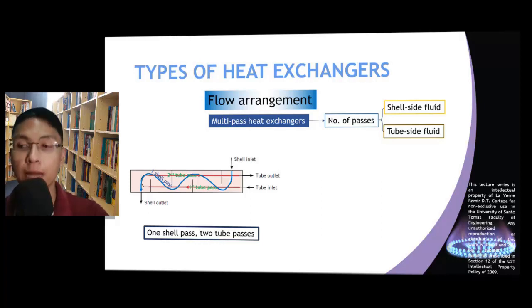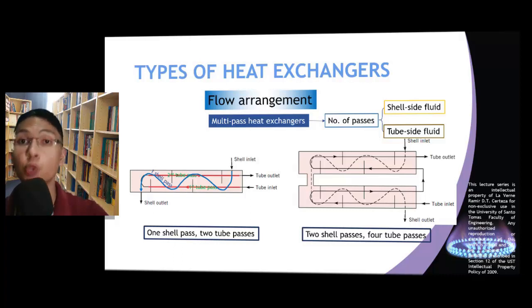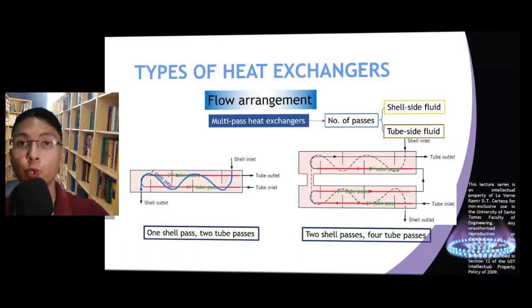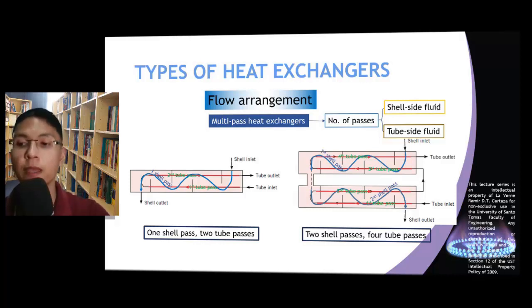Another example is the two-shell-passes, four-tube-passes heat exchanger. From the diagram, the tube-side fluid flows in four different directions: the first tube pass, the second, the third, and the fourth. For the shell-side fluid, it flows first in one direction, then exits in the opposite direction — since it flows in two opposite directions inside the heat exchanger, this gives two shell passes.